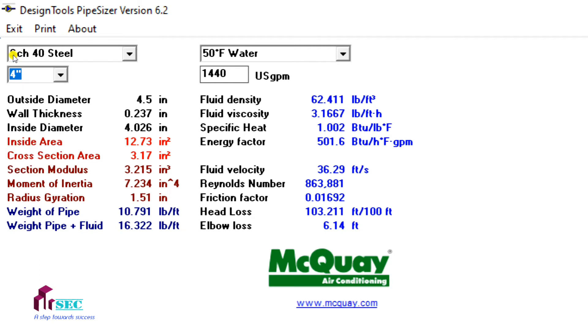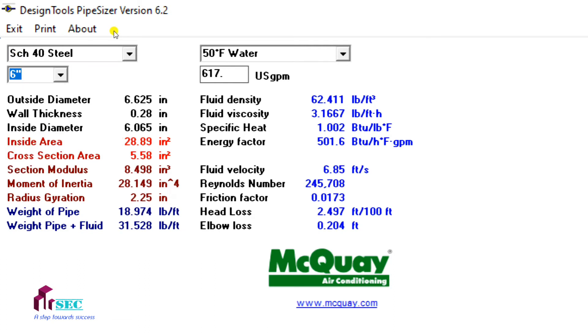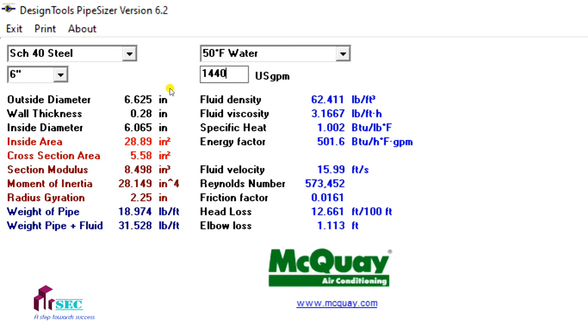So I'm going to check now with 6 inch. Select the 6 inch here and enter the GPM. The fluid velocity is now 15.9 feet per second. That means you have to further increase — it should be less than or equal to 10 feet per second.